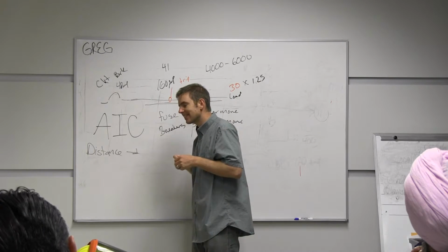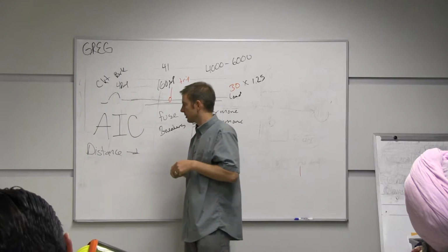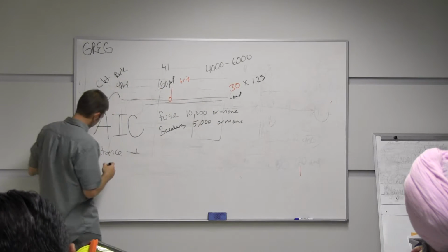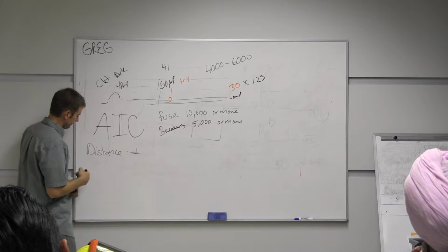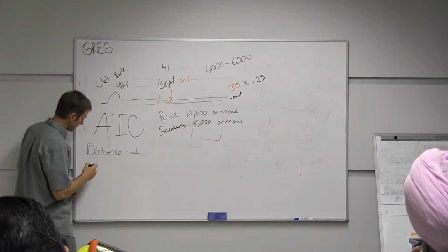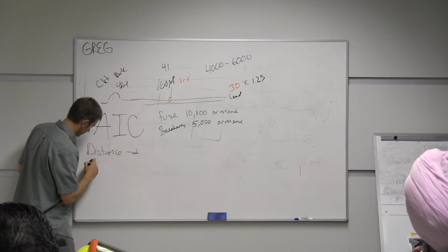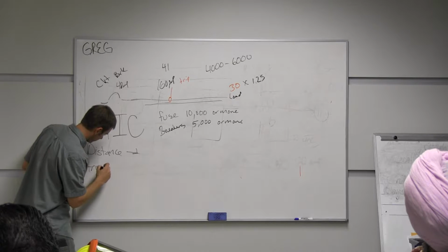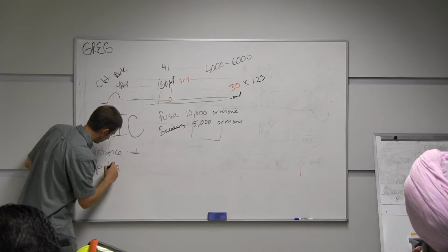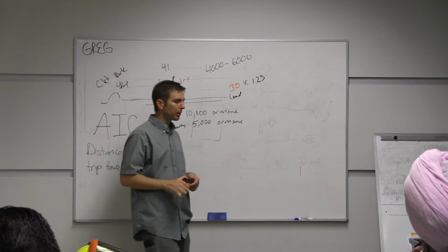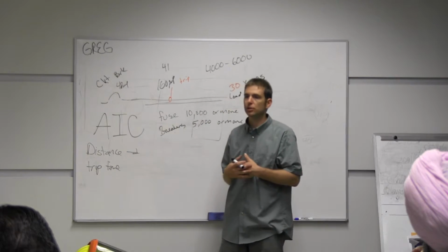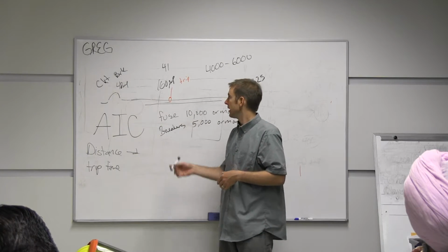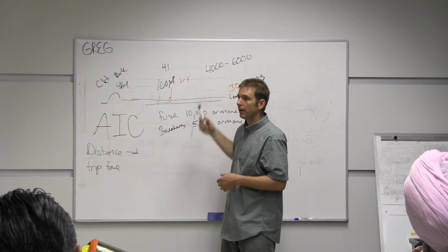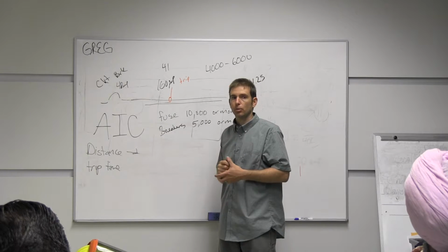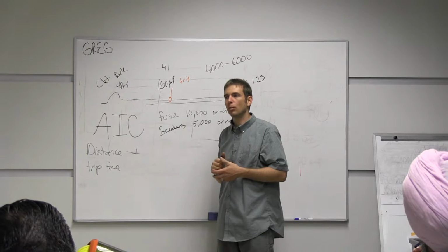Also, the sensitivity of the breakers. So some breakers are instantaneous trip or faster tripping. So we'll call that trip time. So if a circuit breaker or fuse can trip extremely fast, the faster it trips, it reduces the available fault current. And sometimes that's a bad thing.